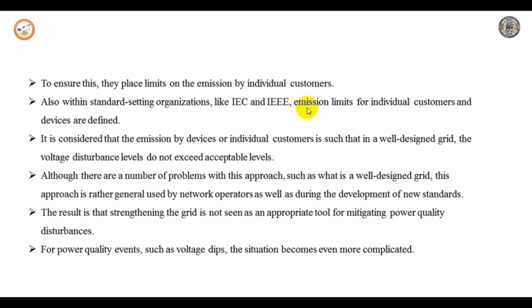So with this we have seen some effects of strengthening the grid. The overall conclusion is that for power quality events such as voltage dips, with an increase in the grid strength, the hosting capacity becomes more and more complicated. So this is about the strengthening of the grid. Now let us see the emission limits for the generator unit.